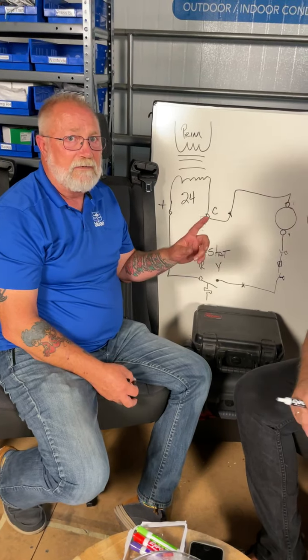If it's chassis grounded, and you went from Y to ground or to chassis ground, if this was closed, yes, theoretically you should read 24 volts. But if it's not chassis grounded and you go from here to chassis ground, then no, it's not going to read. One of the things I like to do is start at the transformer and just read across here to see that I've got my 24 volts. If I've got my 24 volts, what happens if you don't have your 24 volts?